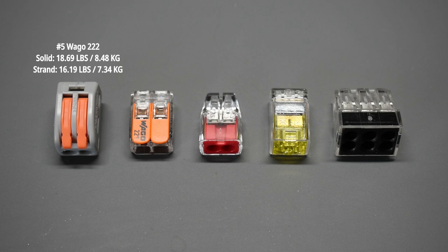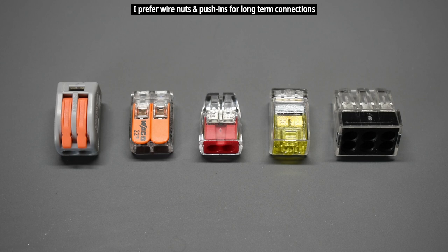The results show that the push-in type connectors have superior holding strength. If you're not looking for a very high level of clamping strength but you want to have a connector that's very easy to install the wires and remove the wires, then the Wagos are the way to go.